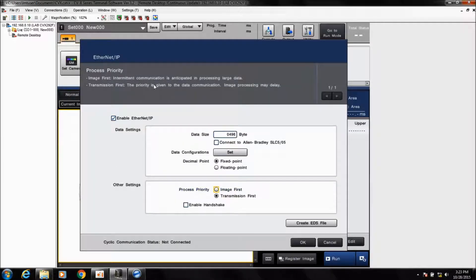Process priority dictates what has priority — whether inspection takes priority over transmission of data, or data has priority. In other words, when there's a backlog of data, you can choose to pause and wait for open space in the buffer, or continue processing and skip data if the buffer fills. You can also enable or disable handshaking here if you want to use that function when outputting data.